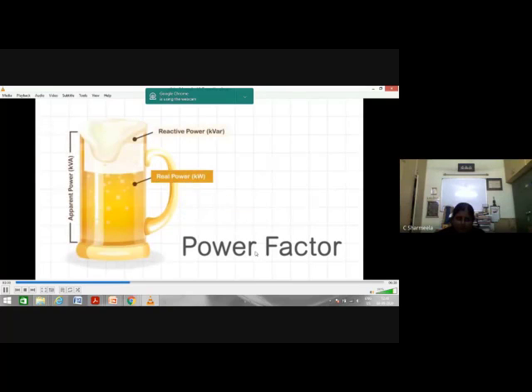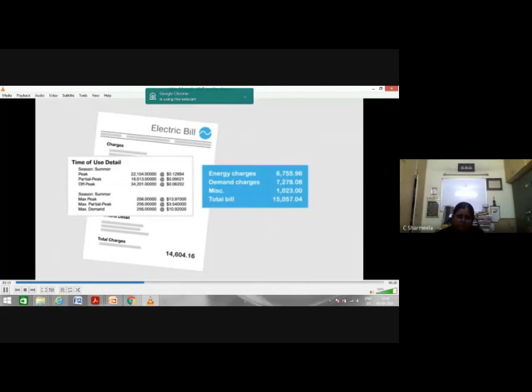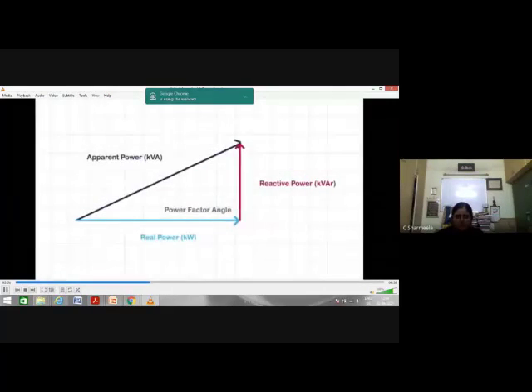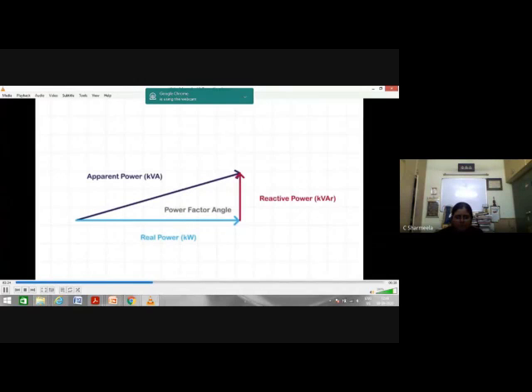Power factor determines how well you utilize your power. It's the simple ratio of your real power over your apparent power. The general engineering practice or rule of thumb is to keep the power factor in an electrical installation above 90%. Why correct power factor? It can reduce utility bills by reducing your demand charges, which relates to your rate structure. It reduces apparent power, therefore reduces loading on your power transformer and distribution network.